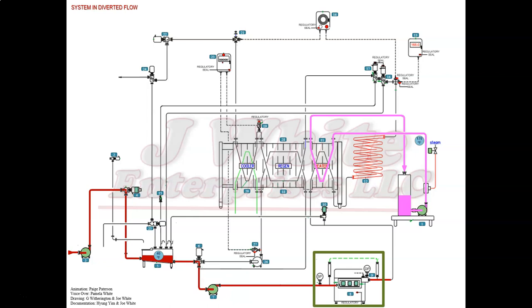The timing device can be a positive displacement pump or a centrifugal pump connected to a magnetic flow meter to ensure that the product will never flow through the holding tube in less than 15 seconds on milk and 25 seconds on ice cream.